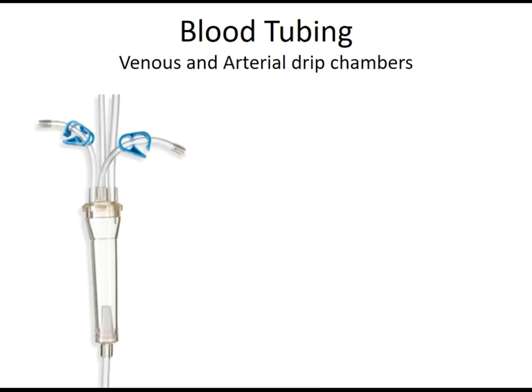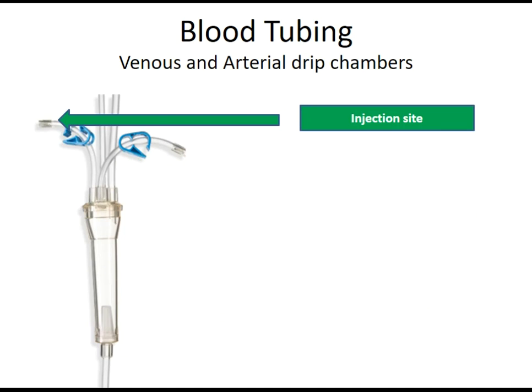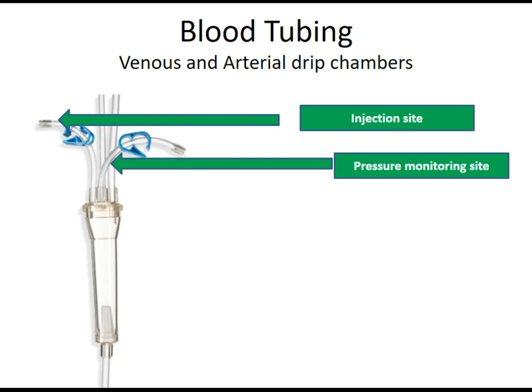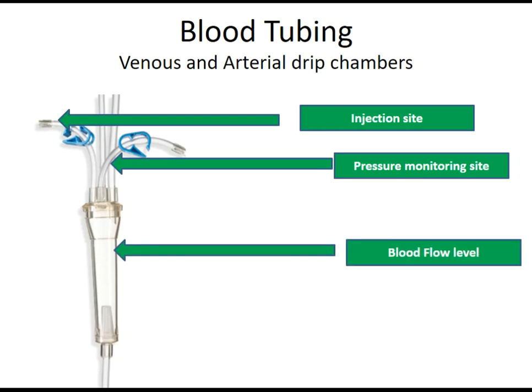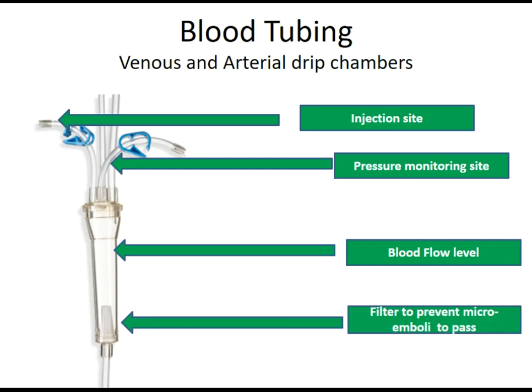The blood tubing venous and arterial drip chambers include an injection site, a pressure monitor site attached to the transducer protector, a blood flow level indicator, and a filter to prevent micro-emboli from passing to the patient.